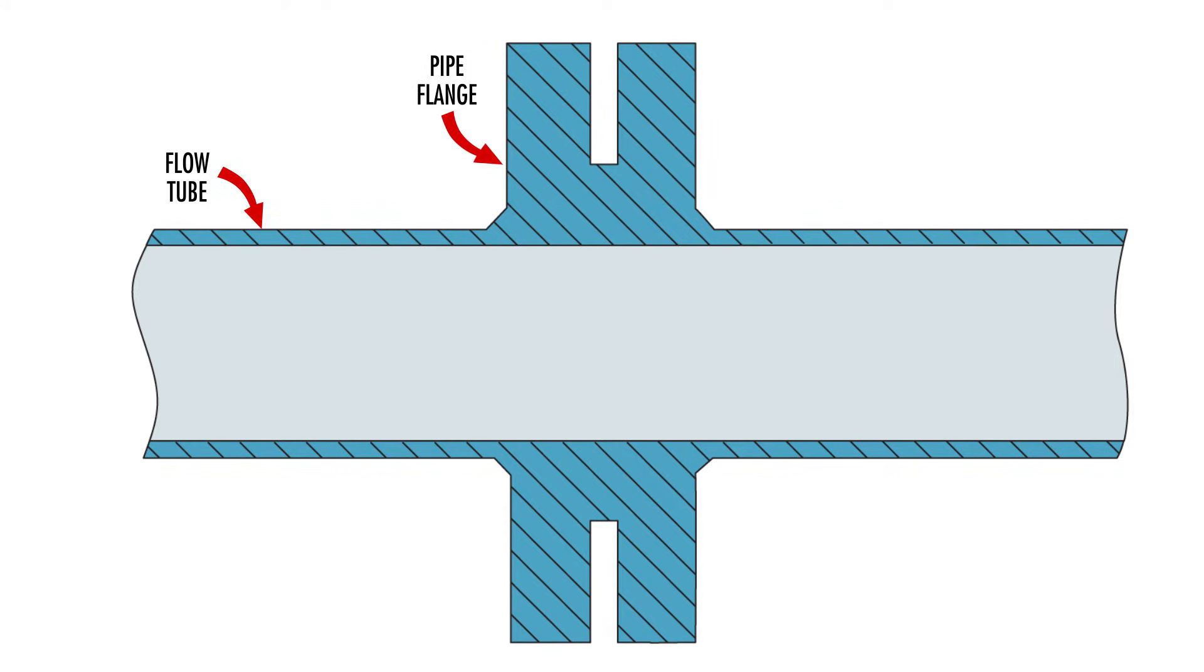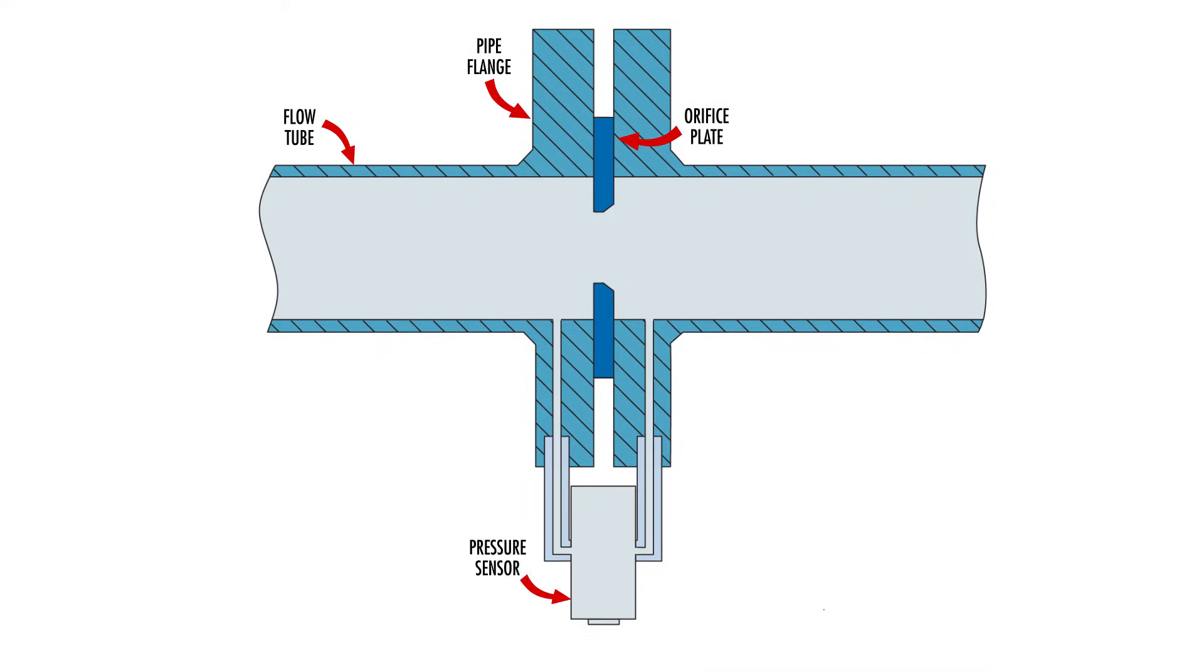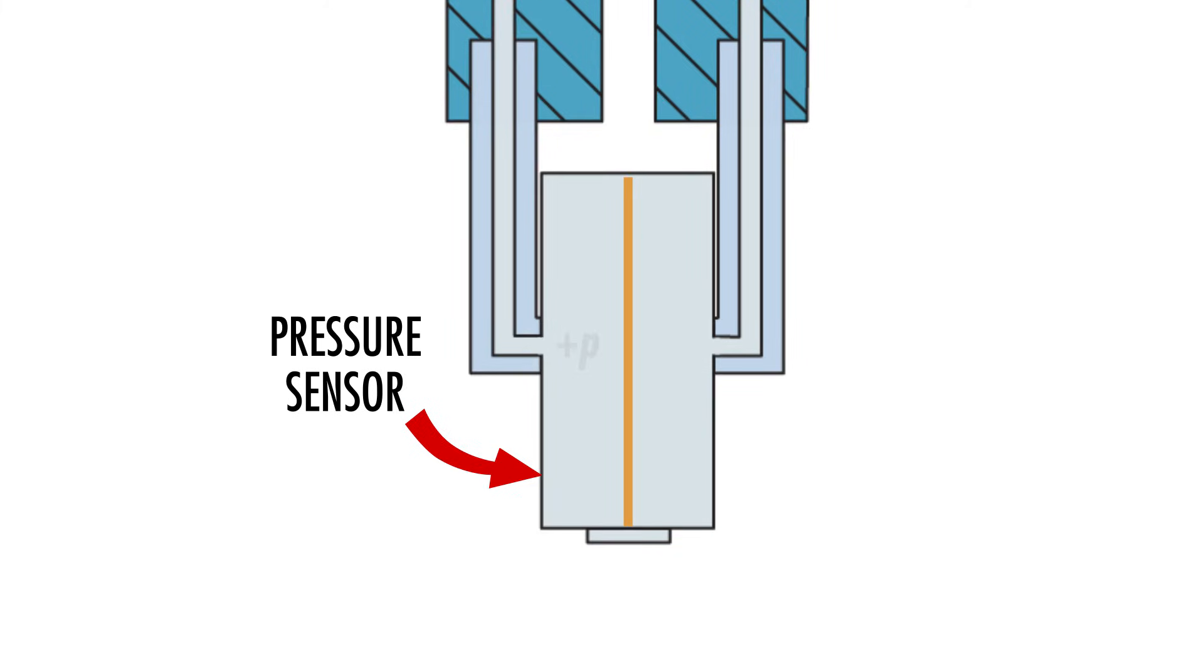Differential flow meters feature an artificial restriction such as this orifice plate. Two holes are located in the pipe walls, one before the restriction and one after. Tubes connect the two holes to a differential pressure sensor whose two pressure chambers are separated by a diaphragm. The sensor detects minute changes in pressure between the two chambers.